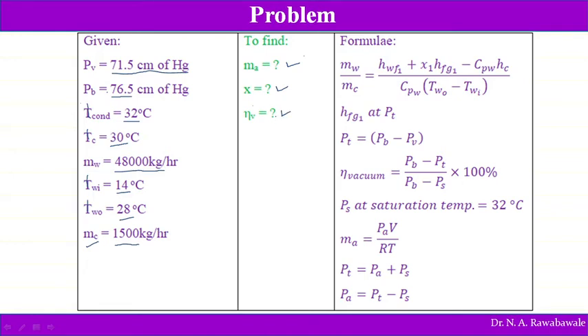To find dryness fraction, we use the heat balance formula containing dryness fraction, ratio of mass flow rate of water to mass flow rate of condensate. Mass flow rate of water (48,000 kg/hr) and condensate (1500 kg/hr) are known. HF and HFG must be taken at total condenser pressure PT, which must be calculated first. Specific heat of water CPW is 4.2 kJ/kg·K.